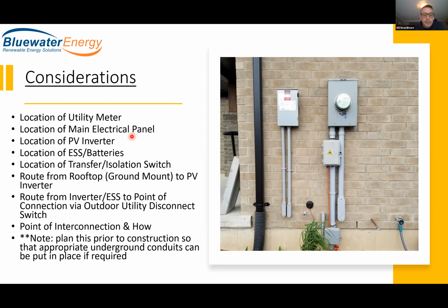We want to consider where the PV inverter is going, where the batteries are going, if any. And I'm going to talk about some limitations with regards to that shortly. Also the location of the transfer isolation switch, if we're employing such a device, and we do have to when batteries are being installed. The route from the rooftop to the PV inverter, and the route from the inverter to the point of connection via the outdoor utility disconnect switch. We need to have one of these for every project, and it has to be located within 1 meter of the utility meter. Essentially we come out from the inverter and then go back inside, and it's simply a disconnect that shuts the system down from the outside, for the utility or whoever wants to do so. This is planned prior to construction so that the appropriate underground conduits can be put in place if required.